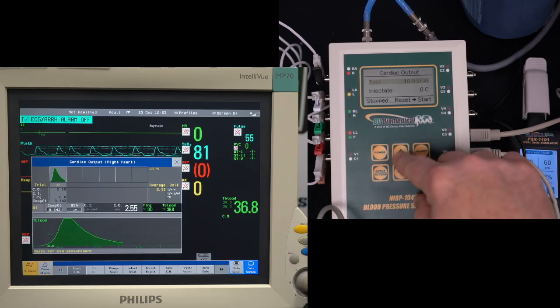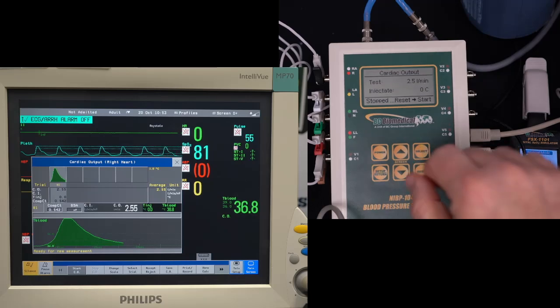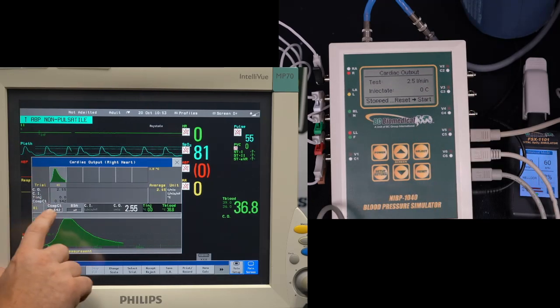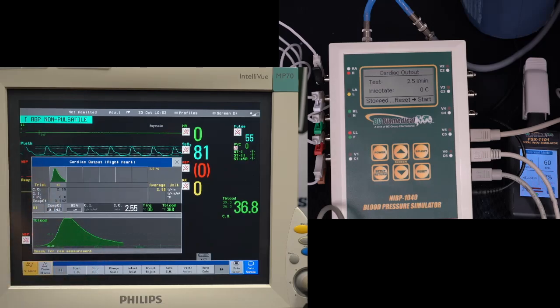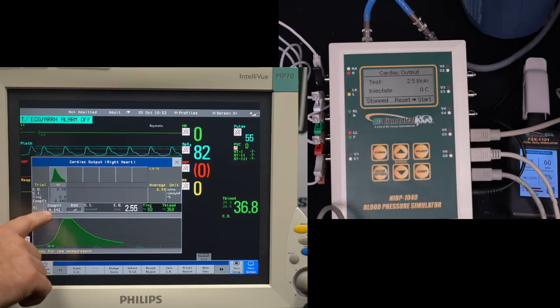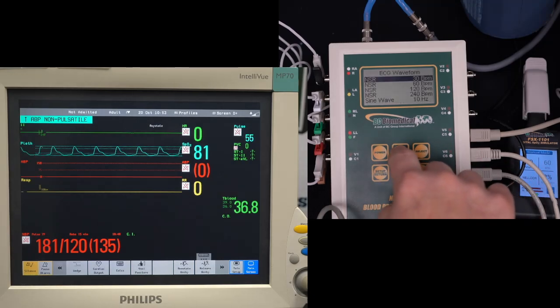And again, we can easily go in and adjust these using the select button and start a new test if we need to. Now, the important thing is this coefficient, the computational coefficient. That needs to match 0.542. That is in the user manual for the NIBP. If they use different catheters or different computation constants, it will change the results. So we want to make sure that our simulation is configured for 0.542, so I need to make sure the monitor is also configured. And that's how we can do cardiac output.